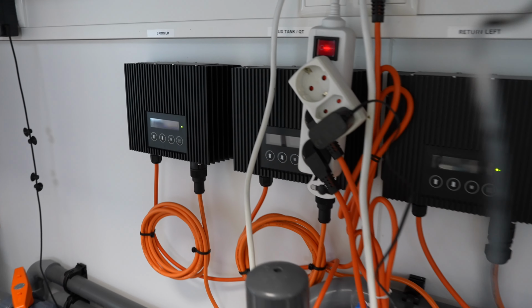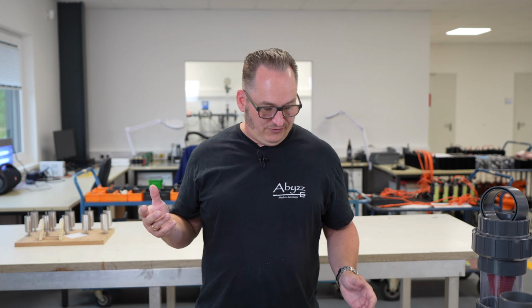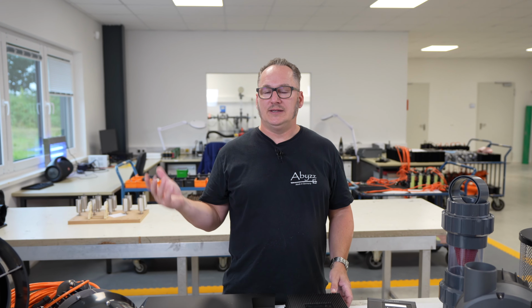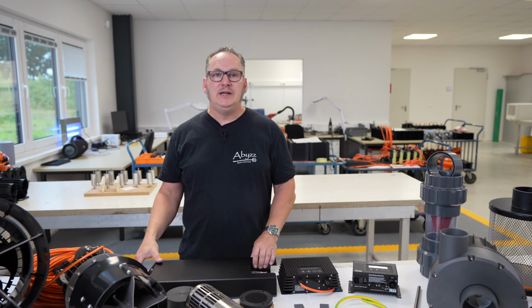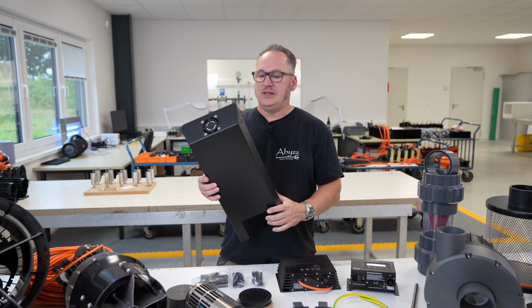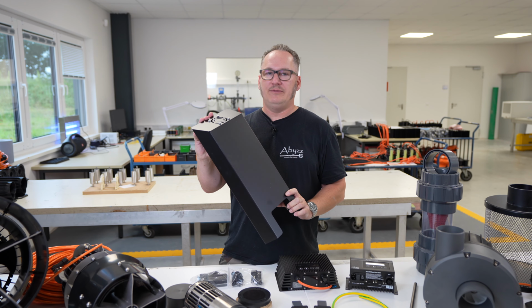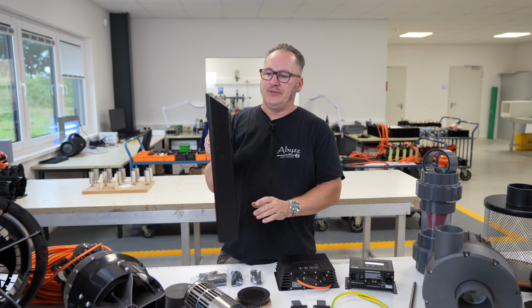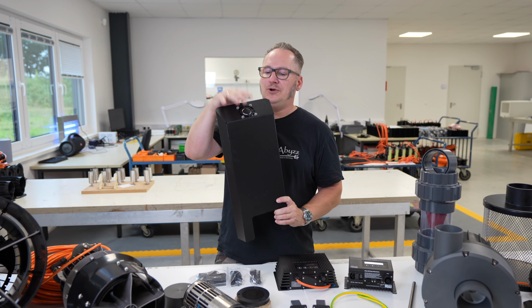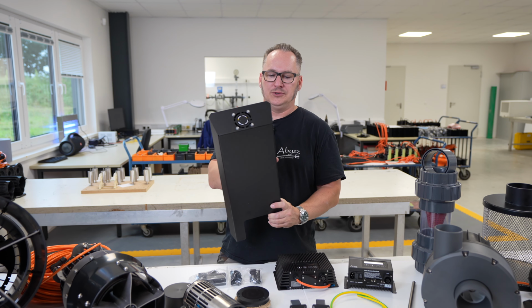If you're running these drivers with a higher ambient temperature than 30 degrees Celsius, we recommend to either have a fan blowing in the direction to get some air movement, or if it's really hot around the drivers, then you can use this IPU cooling cover, which slides on top of the driver, and it forces an airflow around those cooling fins.